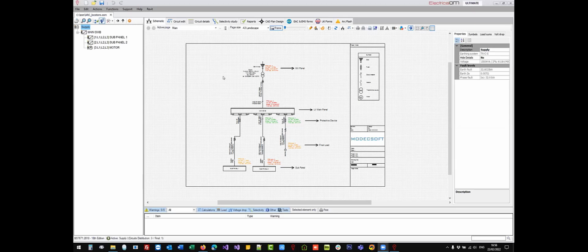As Mike already mentioned, in order to calculate the arc flash study energies and the PPE categories, it's very important to have in place the single line diagram with all the information required to calculate the fault levels, and of course define the necessary devices, which will eventually determine the disconnection times based on the fault levels. And based on all these figures, we will be able to calculate the arc flash incident energies.